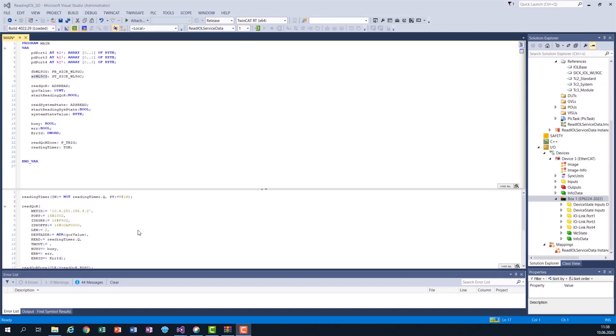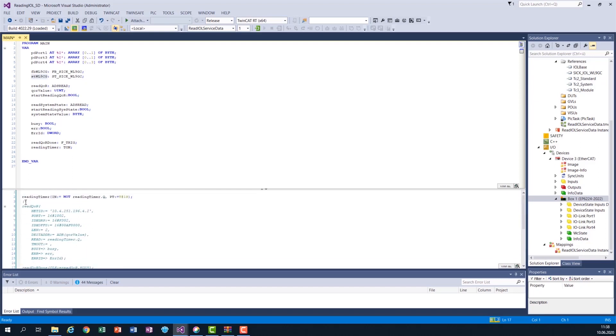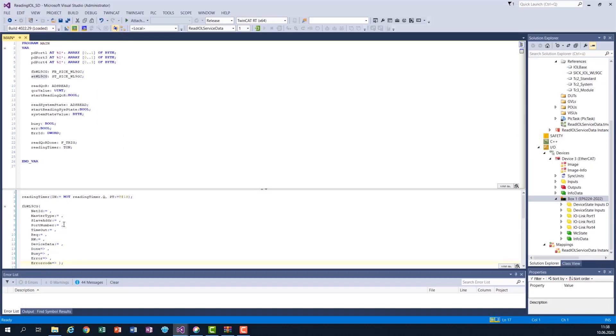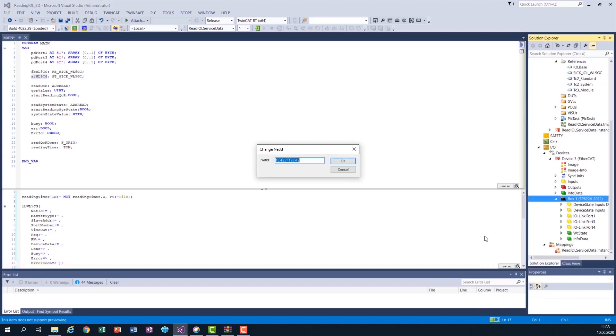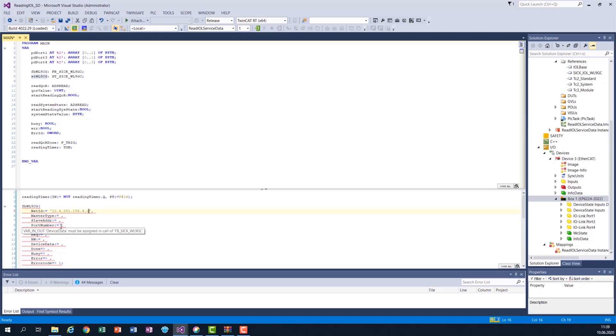We have prepared everything to start programming. First we comment out the older code we no longer need. Then we call our function block using the instance variable. I need the net ID and the address — we get it from here and write it in. We don't need the master type and slave address as we are using the Beckhoff master, so those are default values. Then the port number — the device is connected to port 3, so I type in 3.